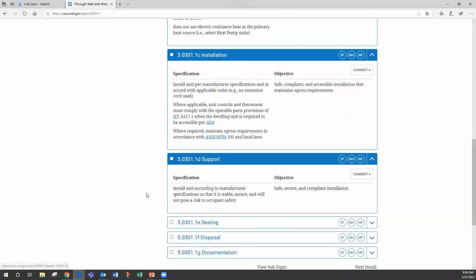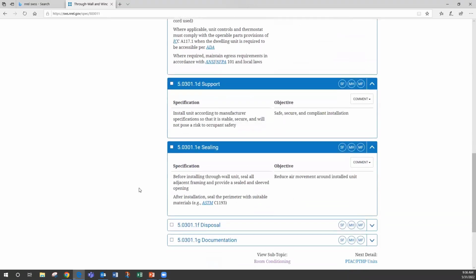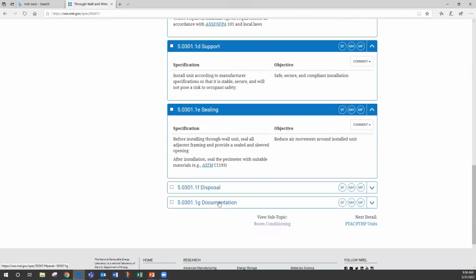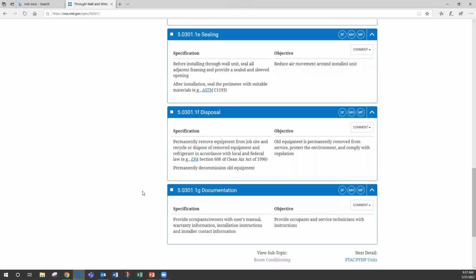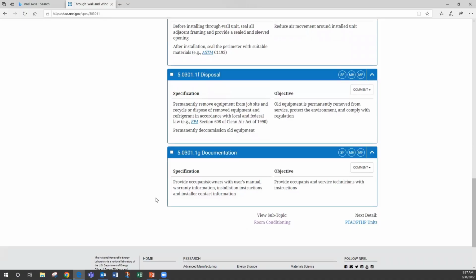And then support talks about how to support the unit, and sealing of the unit: before installing through the wall unit, seal all adjacent framing and provide seals and sleeve opening. So again, this is the guidance. And as far as documentation and disposal, permanently remove equipment from a job site, recycle or dispose of removed equipment and refrigerant. Remember, these units have refrigerant in them, and we follow whatever the local authority having jurisdiction requires, as well as what EPA Section 608 of the Clean Air Act requires us to do. So permanently decommission the equipment. And then as far as what to provide the owners and occupants, at a very minimum, the user's manual, the warranty information, installation instructions, and installer contact information.